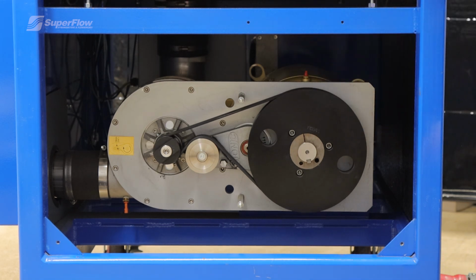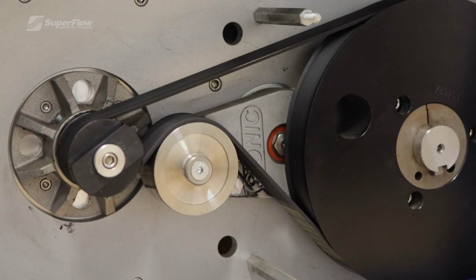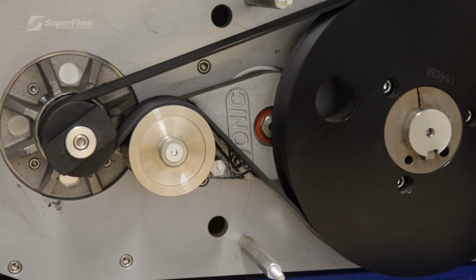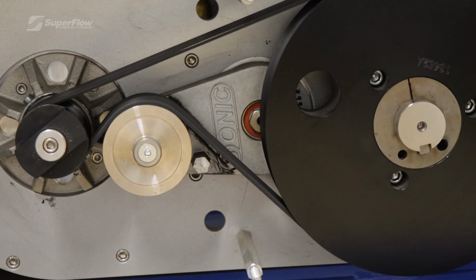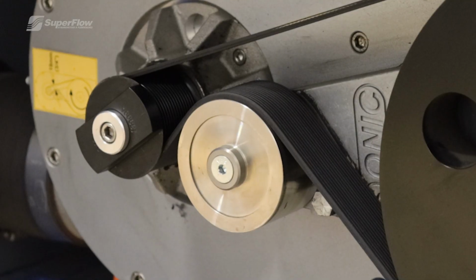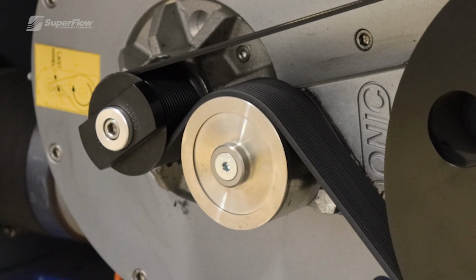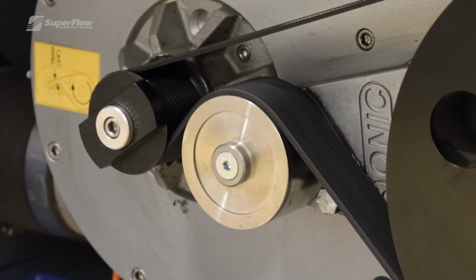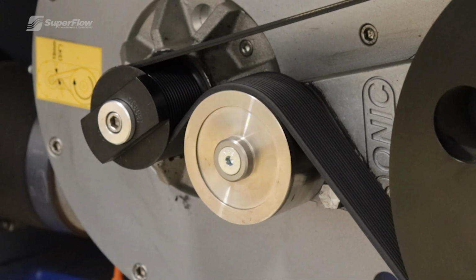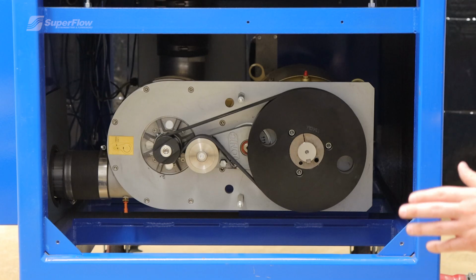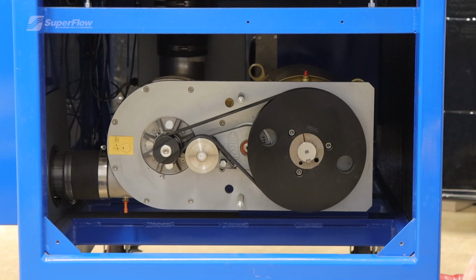This belt should be inspected every 6 months or replaced about once a year, dependent on average usage throughout the year. During your inspection period, if you see any noticeable wear or deficiencies in the belt, it should be replaced immediately. Maintenance on the bench is directly correlated to the accuracy and performance of the flow bench.